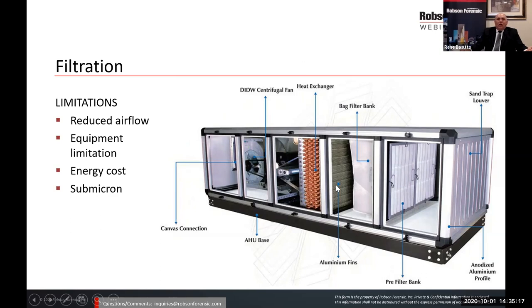And the typical unit will have either a cooling coil and a heating coil, which cool the air or heat the air as it goes through, and then it's discharged down into the space or throughout the space. But again, we're looking at energy costs because of the additional resistance. The higher resistance, the more energy the fans will use and the motors will use to move the air. And we have that limitation, answering that question, is the submicron, the stuff that gets through the filter that can't be completely filtered out. So those are the limitations we have for filtration.